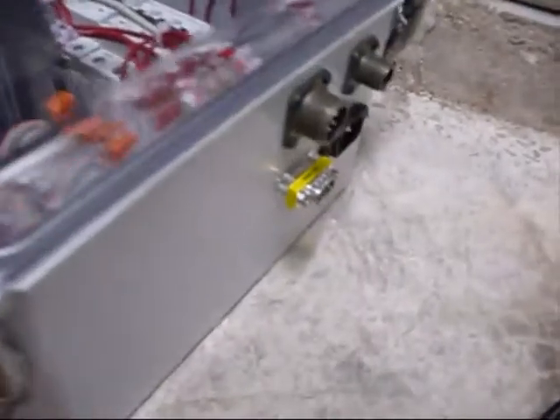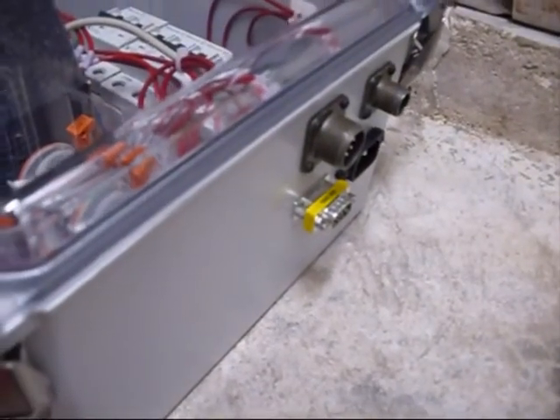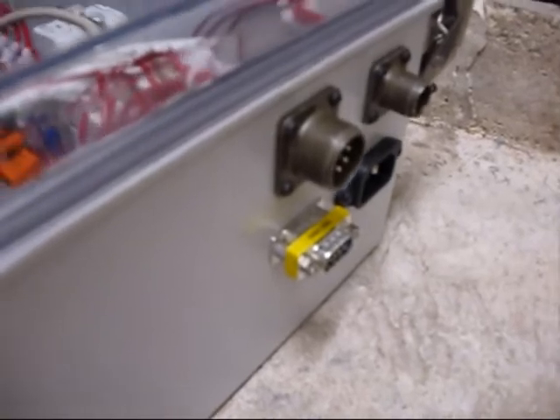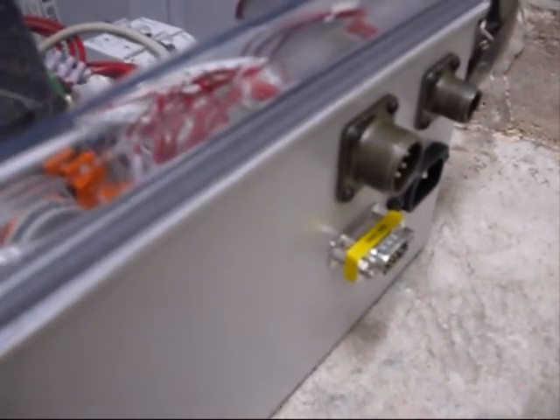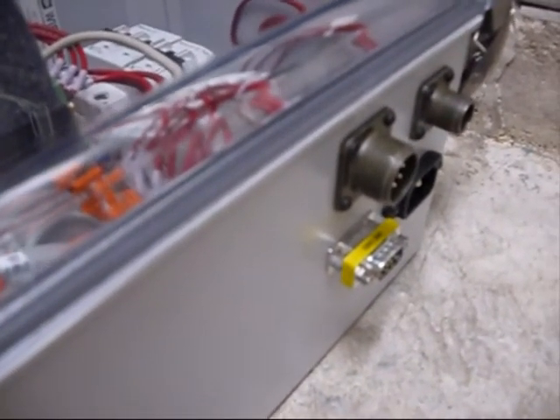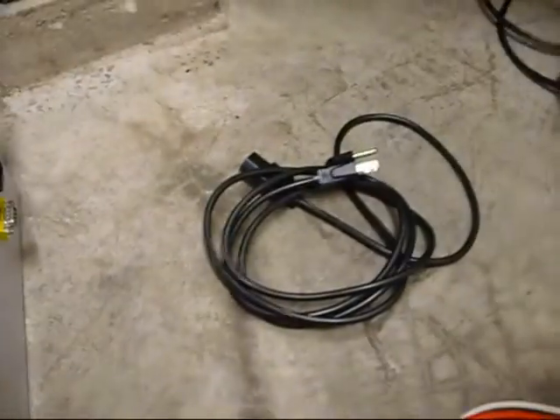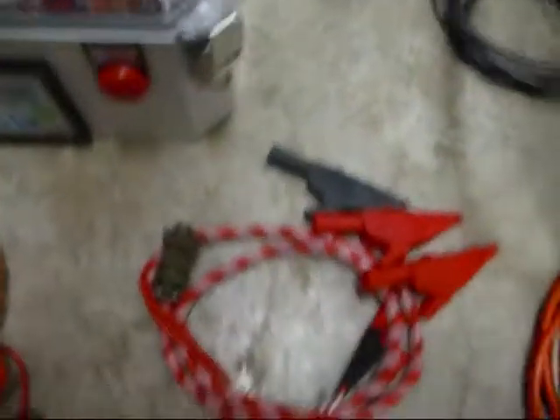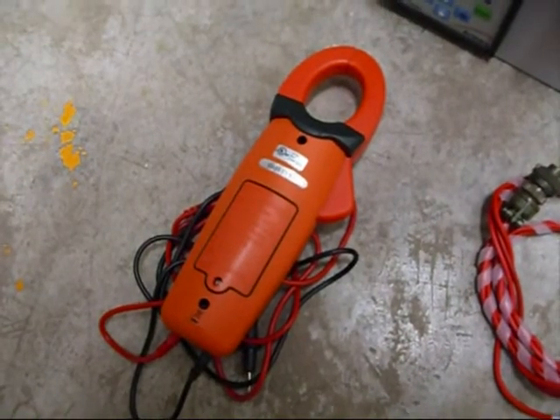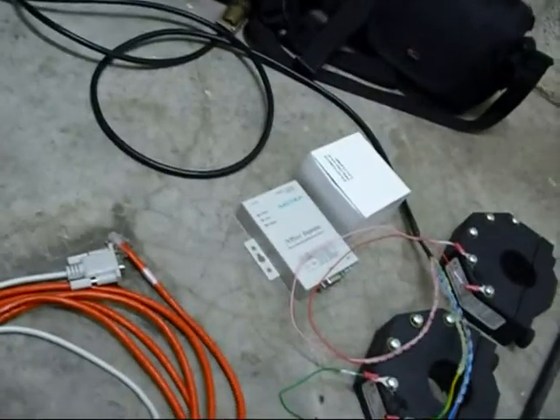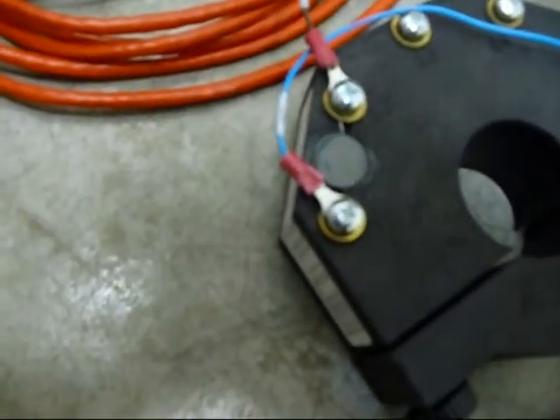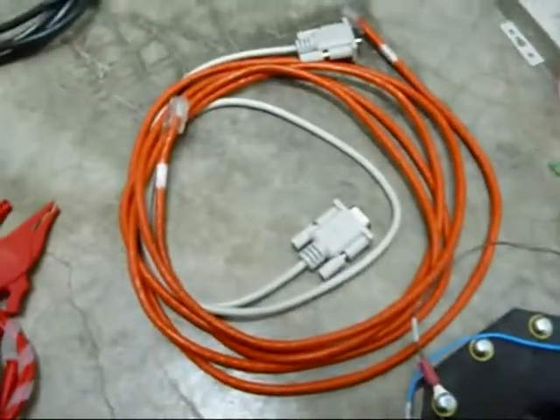We have ports on the side of the box, one for the power, another one for the voltage, another one for the CTs, and another one to connect the MOXA unit. Here we have the power cable, then we have our voltage connections. We're going to do some tests before we start with the voltage and current. We have connection cables for the MOXA and the unit itself, and we've wired the CTs across connection 1 and 2. This selects 100 amps as our primary.